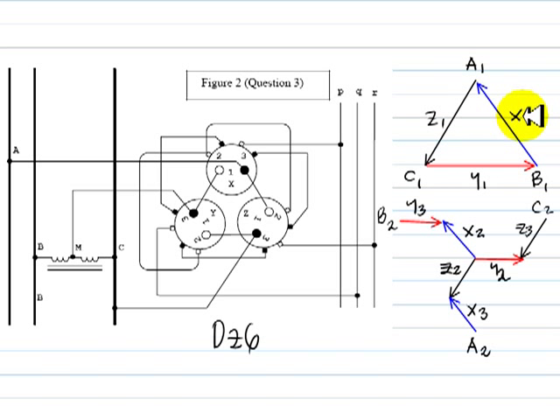Observe. The tip of X1 is connected to phase A. Yes, the tip of X1, this one, is connected to phase A. That checks.